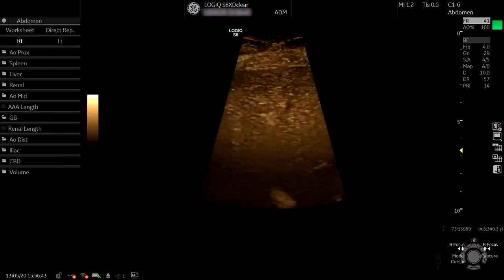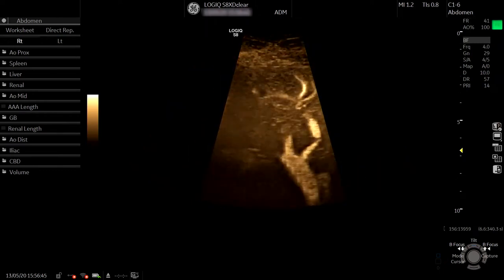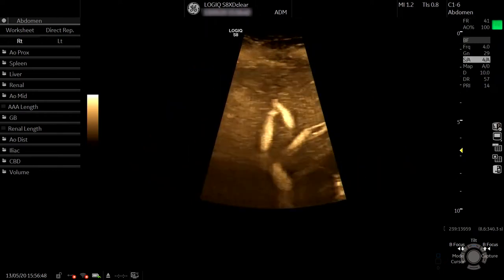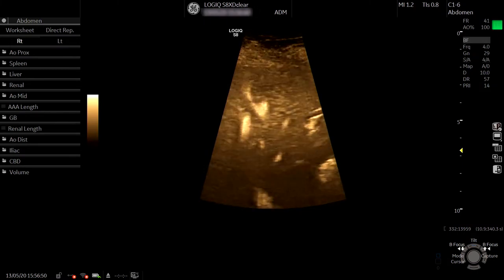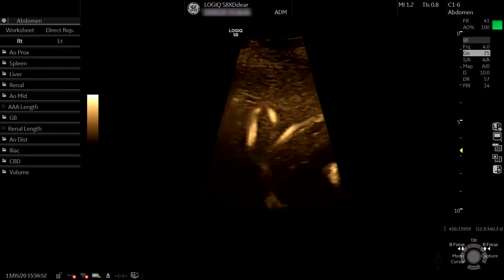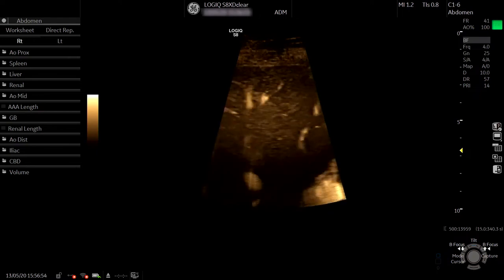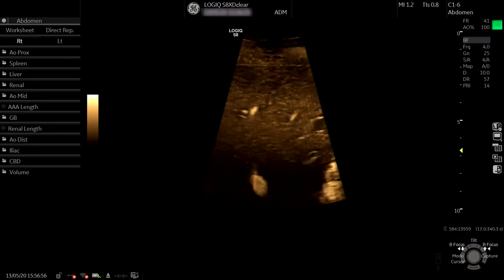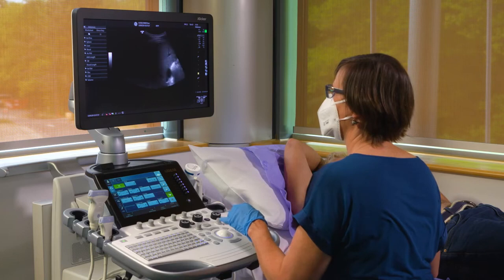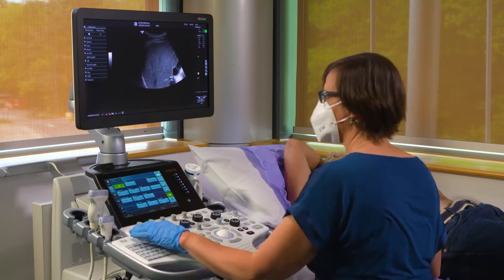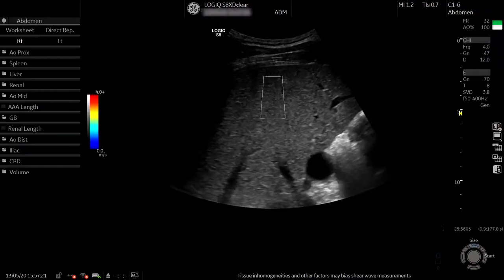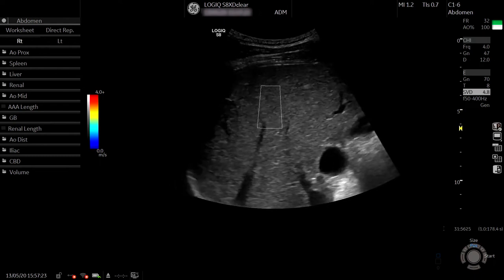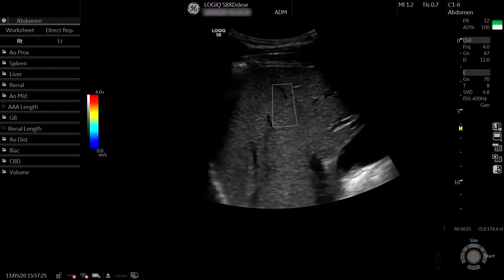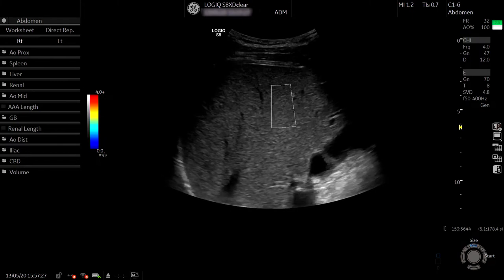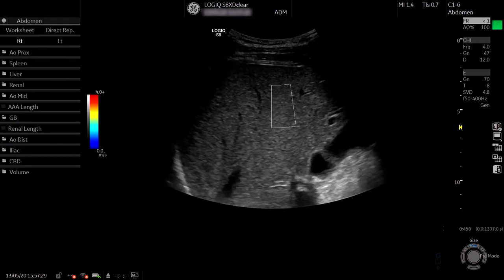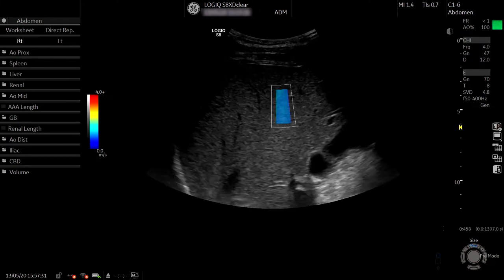We've now added B-flow. B-flow is looking at the hemodynamics of the blood flow and is a 2D technique. This gives no region of interest, higher frame rates and no vessel wall overwriting. We have the facility to perform shear wave on the Logiq S8 with both single and multiple measurements, as well as the ability to display in both meters per second and kilopascals. The shear wave cutoff values can be used for both the Logiq S8 and the Logiq S7.